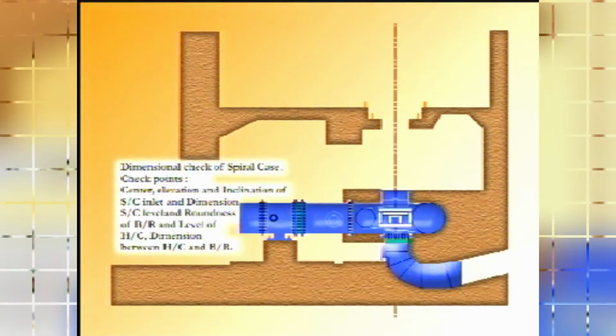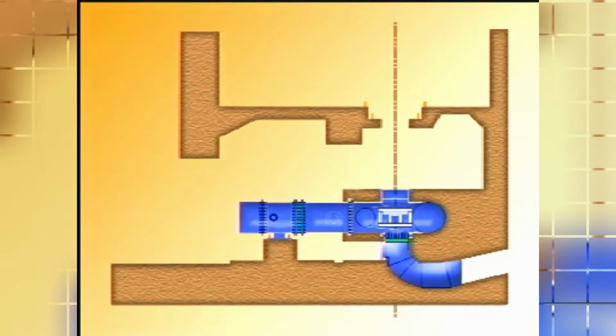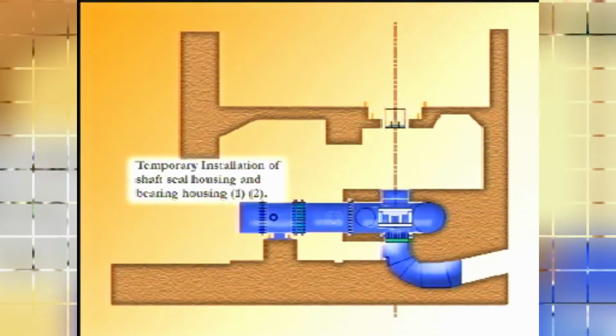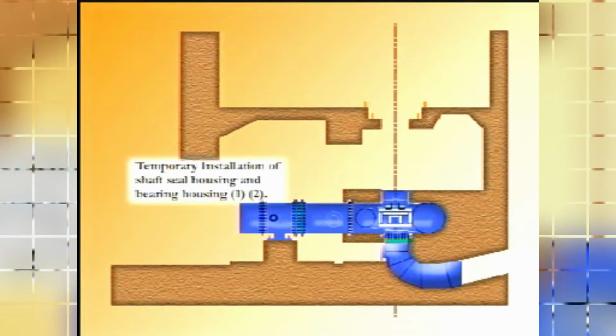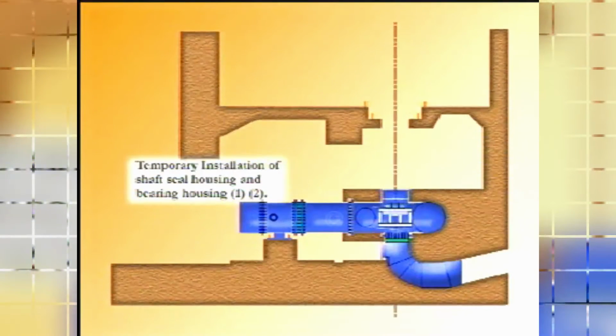Dimensional check of spiral case, checkpoints, center, elevation and inclination of spiral case inlet, and dimension spiral case level and roundness of bottom ring and level of head cover. Dimension between head cover and bottom ring. Temporary installation of shaft seal housing and bearing housing.